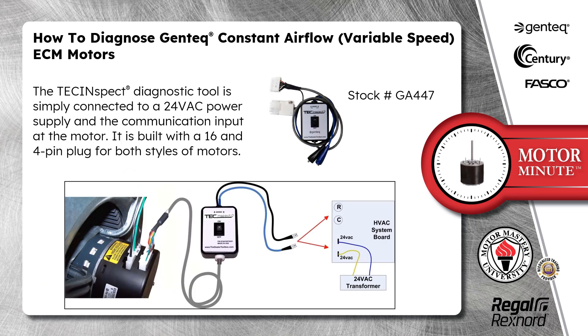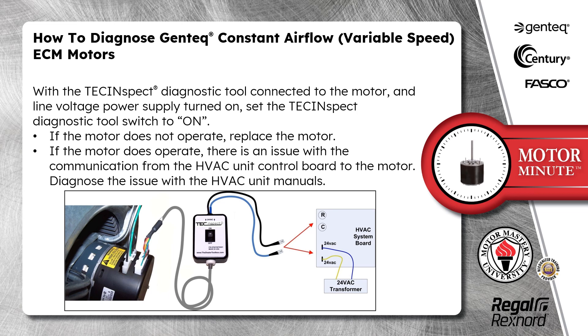The TECINspect diagnostic tool is simply connected to a 24-volt AC power supply and the communication input at the motor. It is built with a 16-pin and 4-pin plug for both styles of motors. With the TECINspect diagnostic tool connected to the motor and the line voltage power supply turned on, set the TECINspect diagnostic tool switch to on.